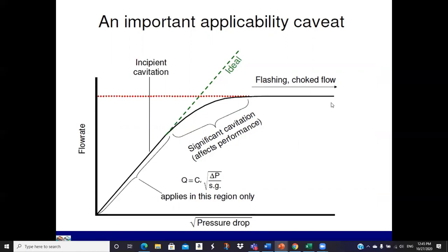So if you're doing something that's pretty critical, you would want to check with the valve manufacturer and find out exactly, for his valve, where this flashing, this choke flow effect, starts to affect the flow rate versus the pressure relationship.